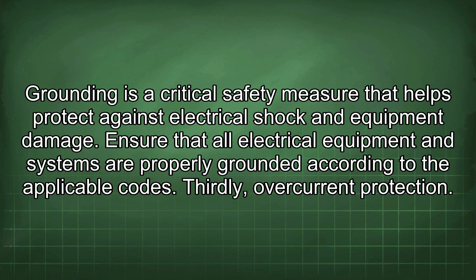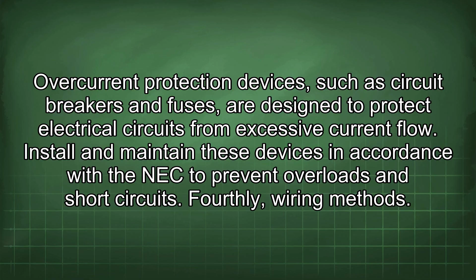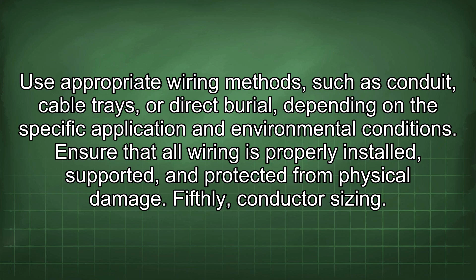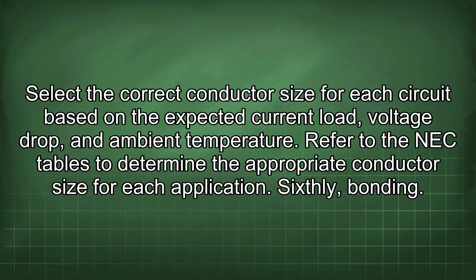Thirdly, overcurrent protection. Overcurrent protection devices, such as circuit breakers and fuses, are designed to protect electrical circuits from excessive current flow. Install and maintain these devices in accordance with the NEC to prevent overloads and short circuits. Fourthly, wiring methods. Use appropriate wiring methods, such as conduit, cable trays, or direct burial, depending on the specific application and environmental conditions. Ensure that all wiring is properly installed, supported, and protected from physical damage. Fifthly, conductor sizing. Select the correct conductor size for each circuit based on the expected current load, voltage drop, and ambient temperature. Refer to the NEC tables to determine the appropriate conductor size for each application.